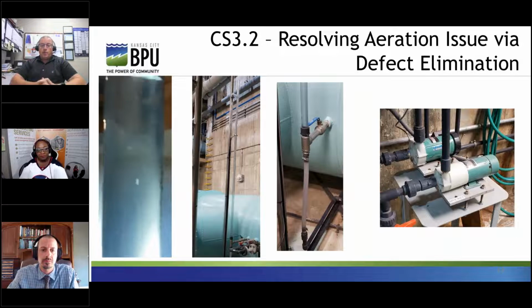So the pumps had already been moved away from the sample point in previous work, so we isolated the analyzers, disconnected the sample lines from the corp stop and valve, and connected a 1-inch clear PVC tubing and let it drain to the floor. It was immediately apparent that air was the cause of the problem. So in this video, I don't know if we'll reshow, you can see the air that was actually going through the tube when we were looking at.